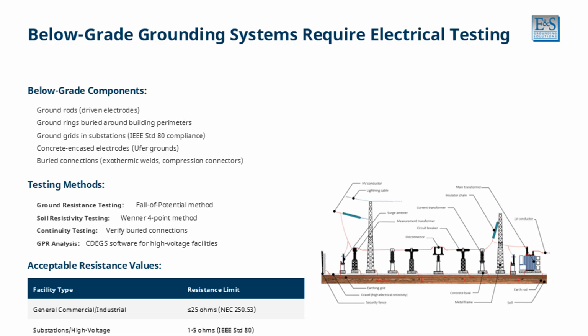Below-grade grounding systems require electrical testing to verify integrity. These systems include ground rods or driven electrodes, ground rings buried around building perimeters, ground grids in substations complying with IEEE Standard 80, concrete-encased electrodes known as UFER grounds, and buried connections using exothermic welds or compression connectors.